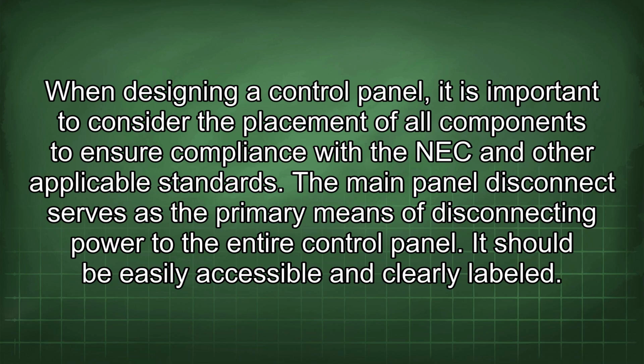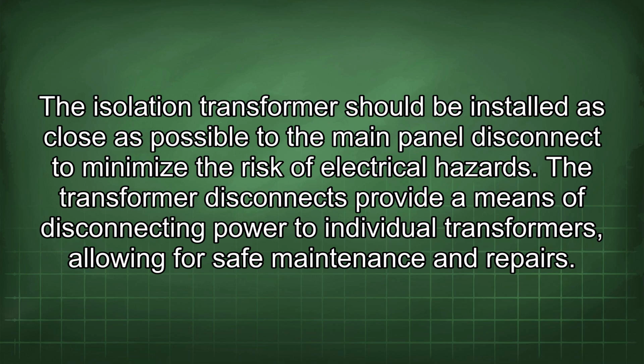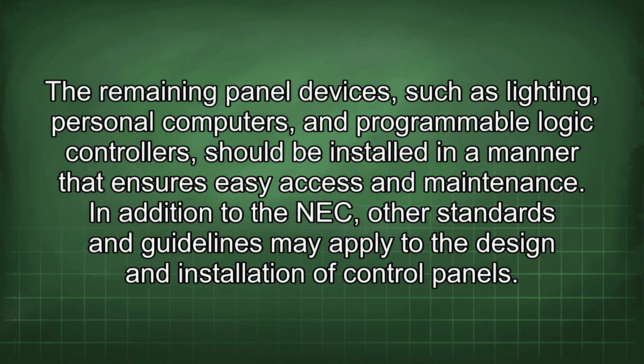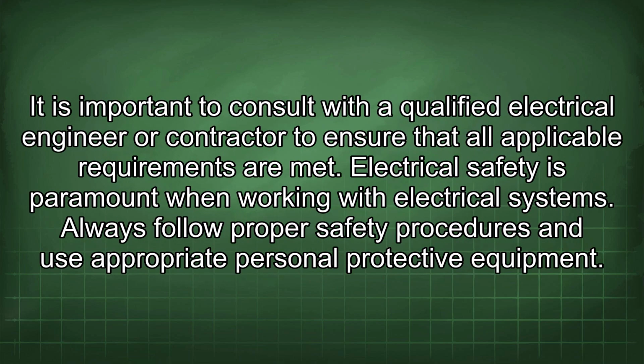The main panel disconnect serves as the primary means of disconnecting power to the entire control panel. It should be easily accessible and clearly labeled. The isolation transformer should be installed as close as possible to the main panel disconnect to minimize the risk of electrical hazards. The transformer disconnects provide a means of disconnecting power to individual transformers, allowing for safe maintenance and repairs. The remaining panel devices, such as lighting, personal computers, and programmable logic controllers, should be installed in a manner that ensures easy access and maintenance. In addition to the NEC, other standards and guidelines may apply to the design and installation of control panels. It is important to consult with a qualified electrical engineer or contractor to ensure that all applicable requirements are met.